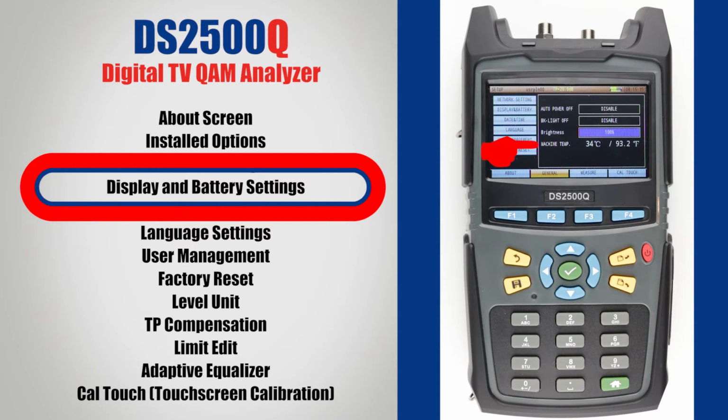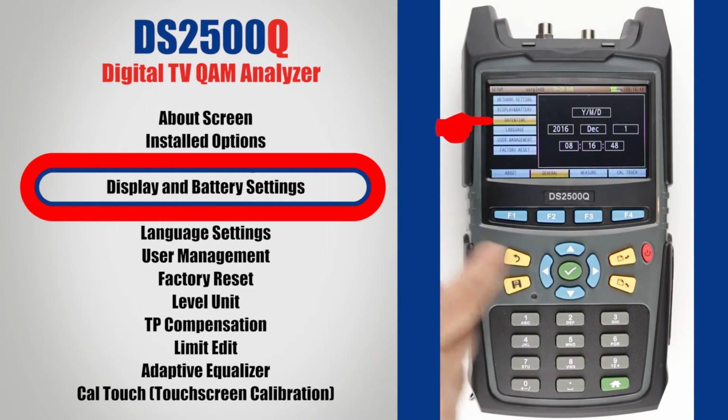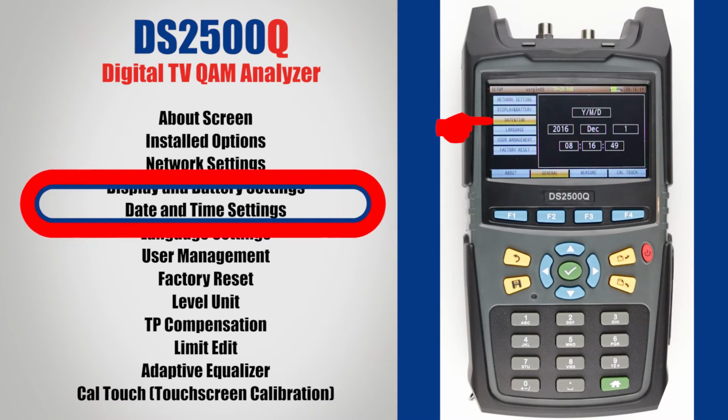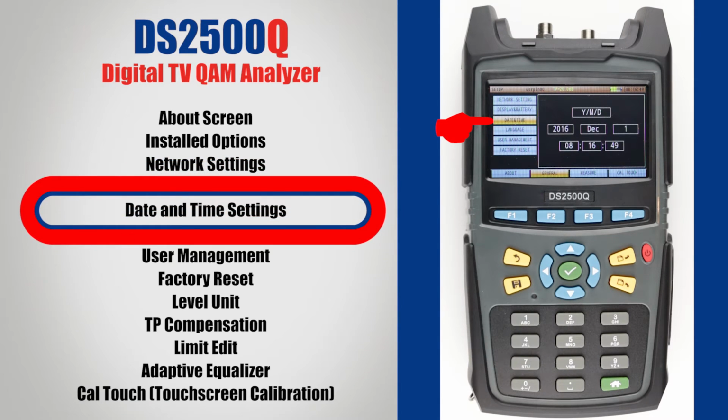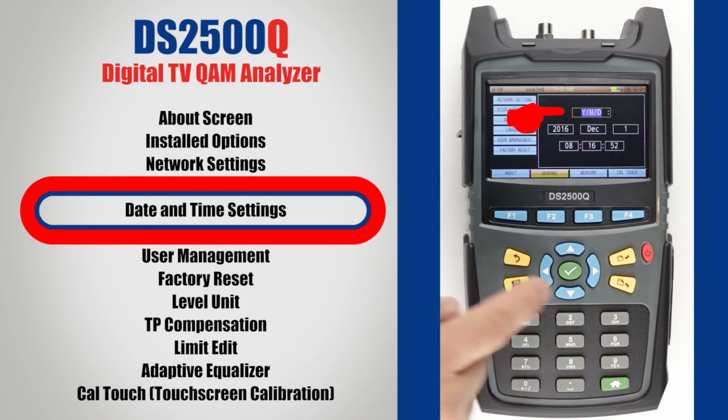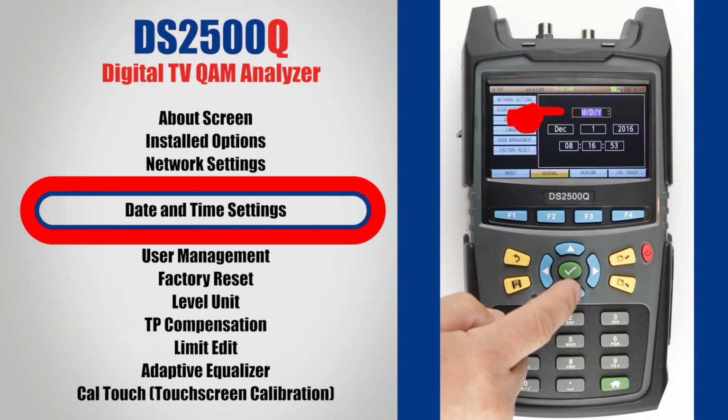Machine temp. This area shows the internal temperature of the instrument. No user entry is needed. Pressing the back key brings us back to the settings selections. Date and time. This page allows you to set the instrument's internal clock. The right and left arrow key will highlight each entry area, and the up and down key will change the settings. The uppermost field area allows you to change the date format. Note that the time is in 24-hour format.